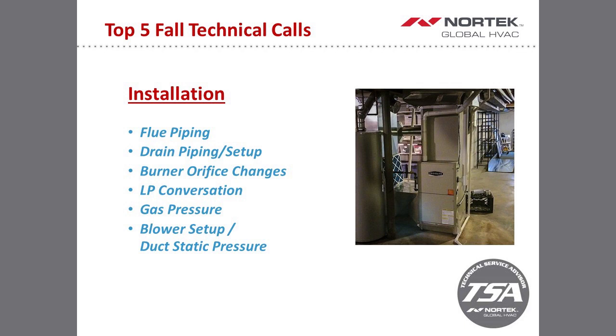If you're on the fixed speed side, like our FG motors, you will have to take a duct static pressure and then look at the blower chart to see where your CFM falls. So those are the two main differences between the variable and the fixed speed ECM motor side. On the PSC side, you can find this information in the tech specs of the furnace. Again, you're basing that on a duct static pressure. That is an important piece of information you need to confirm your CFM output on the furnace. Those are the top things we get questions on for the installation portion of the furnaces.